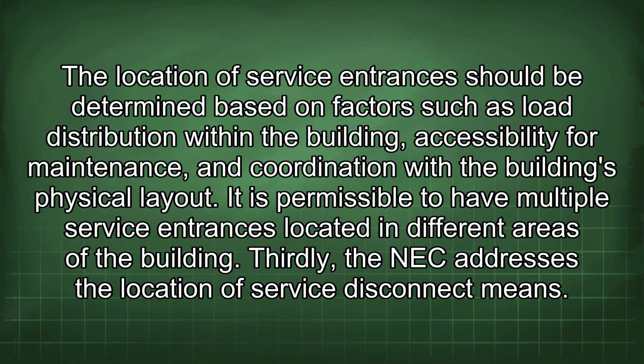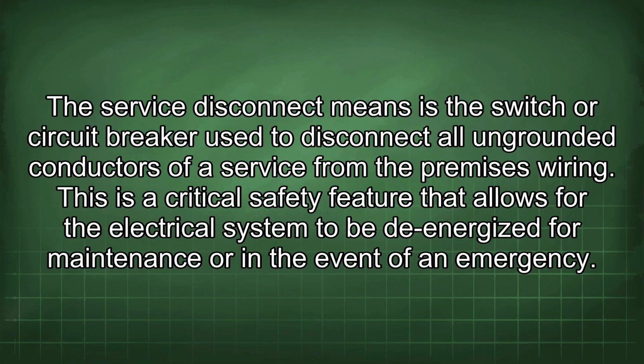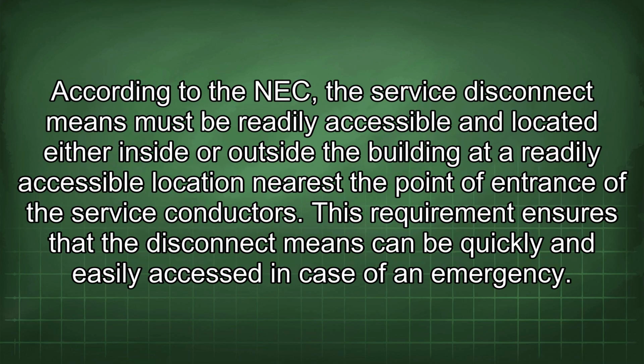Thirdly, the NEC addresses the location of service disconnect means. The service disconnect means is the switch or circuit breaker used to disconnect all ungrounded conductors of a service from the premises wiring. This is a critical safety feature that allows for the electrical system to be de-energized for maintenance or in the event of an emergency. According to the NEC, the service disconnect means must be readily accessible and located either inside or outside the building at a readily accessible location nearest the point of entrance of the service conductors. This requirement ensures that the disconnect means can be quickly and easily accessed in case of an emergency.